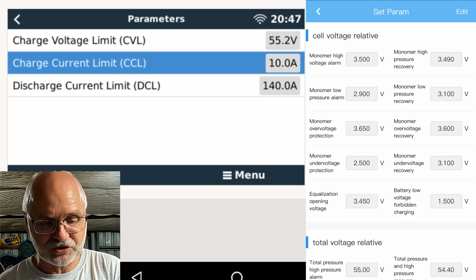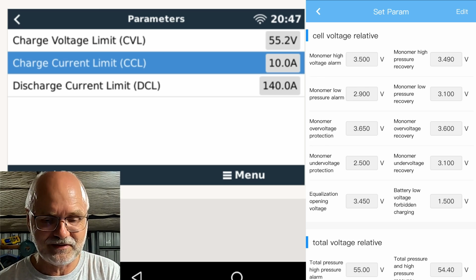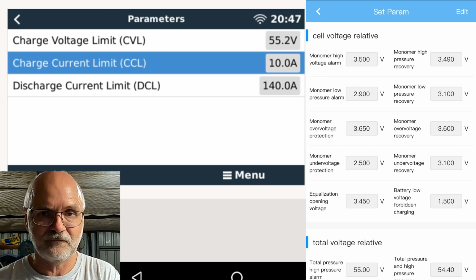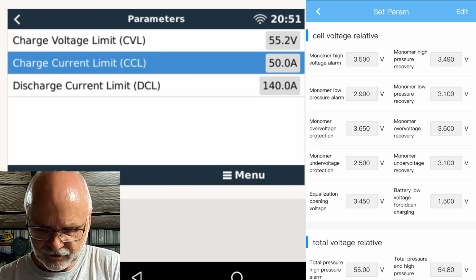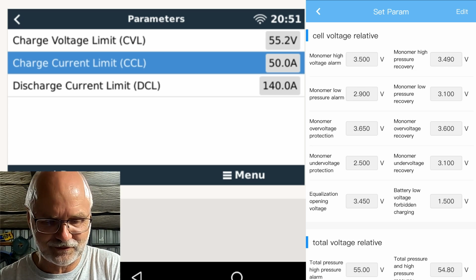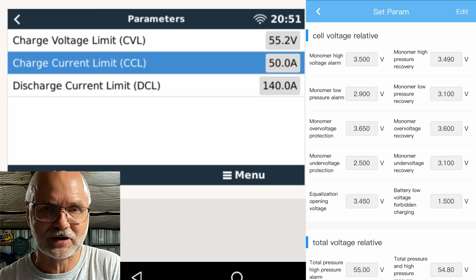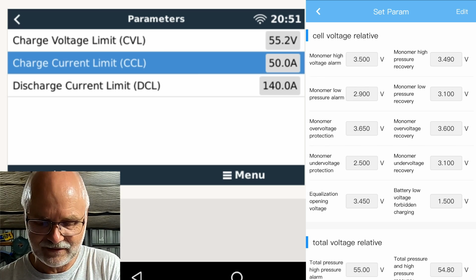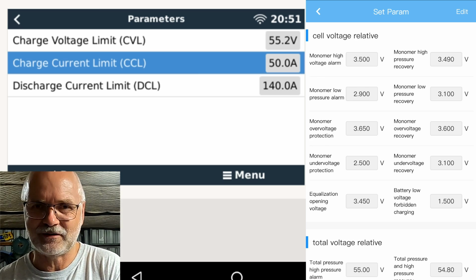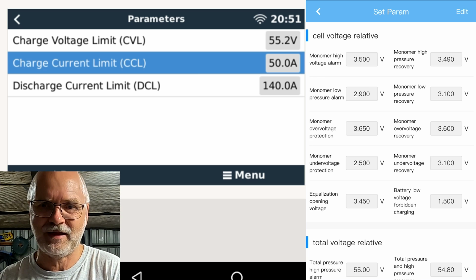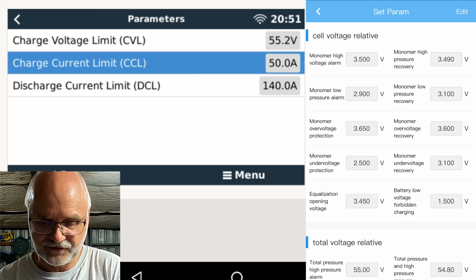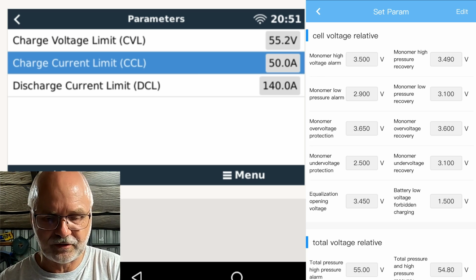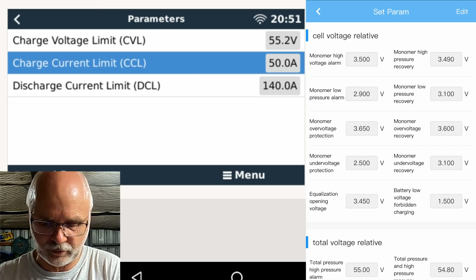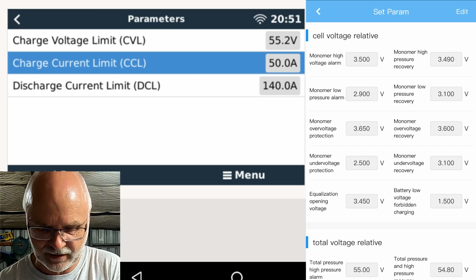Okay, so to change the charge current limit, CCL, in your Victron system, I had to clear this alarm first, because the CCL, the charge current limit, was set to 10 amps. As soon as an alarm occurs, the BMS requests only 10 amps of charging current. So this is all cleared now. So we can see we've got a limit of 50 amps going into the battery then. This is our limit we have set.